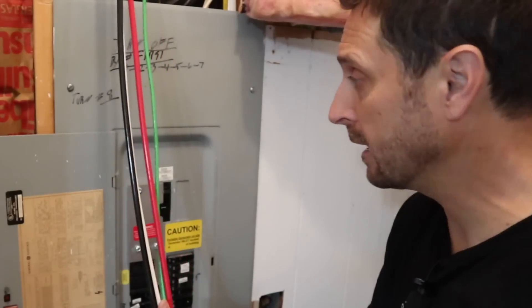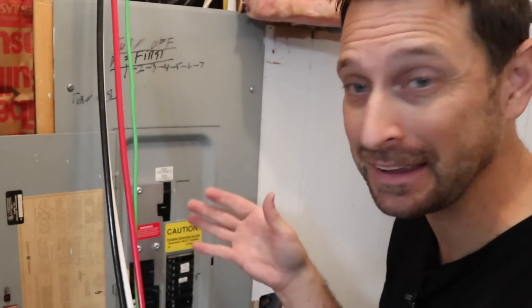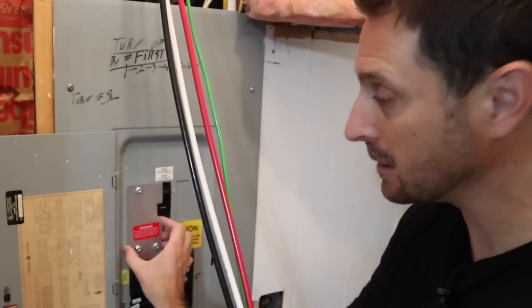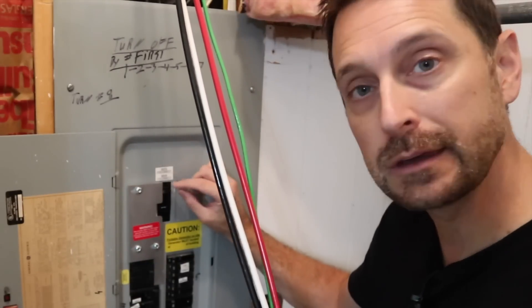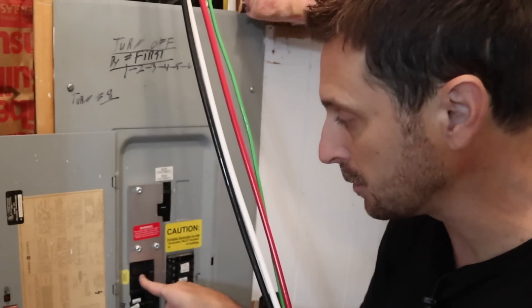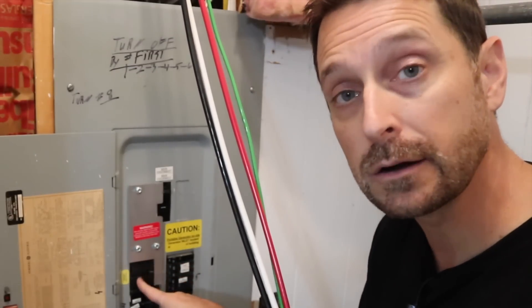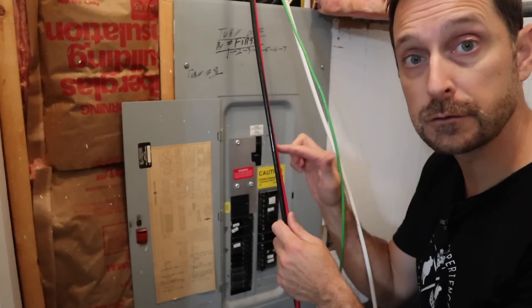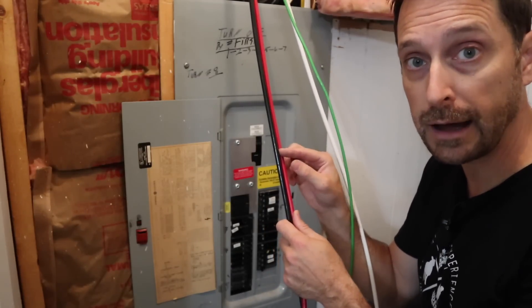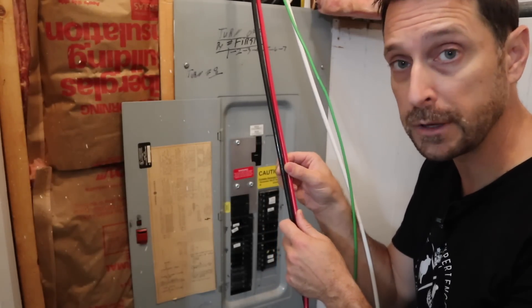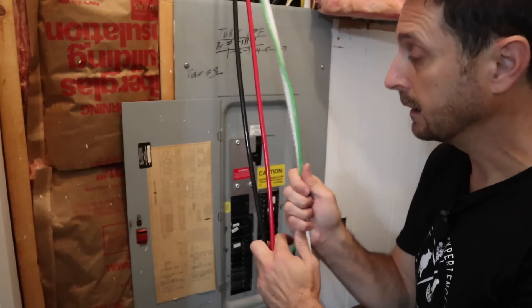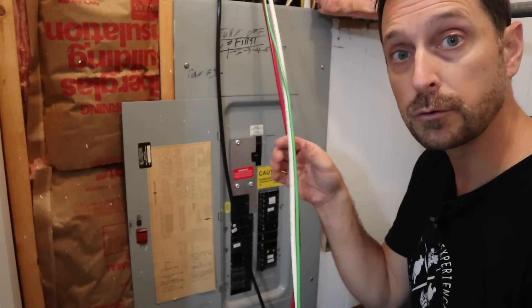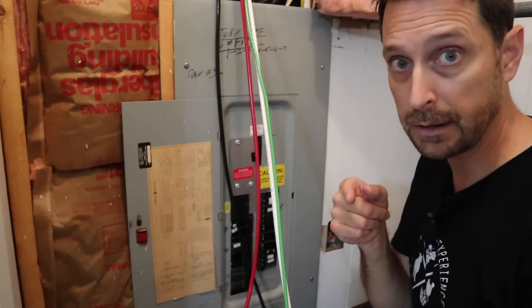Here I am with my main panel. This is the generator interlock kit. It doesn't allow the grid power to be on at the same time as the solar power. That solar power is coming in right here on this 70 amp breaker. I'll have the L1 and L2, the two hots, run from that sub panel, and it's one from each inverter, my ground and my neutral. This is where I'm going to make my ground neutral bond is in this panel and not the sub panel.